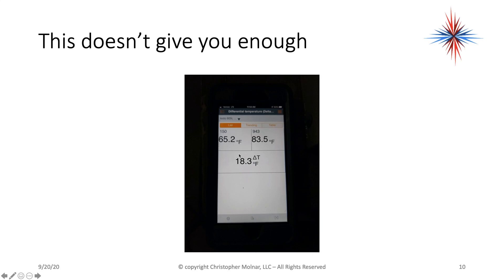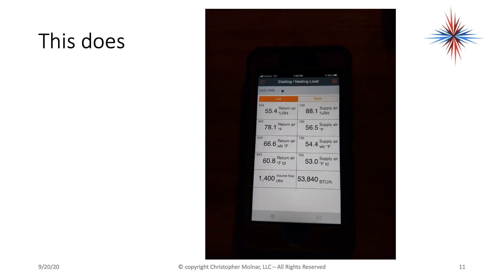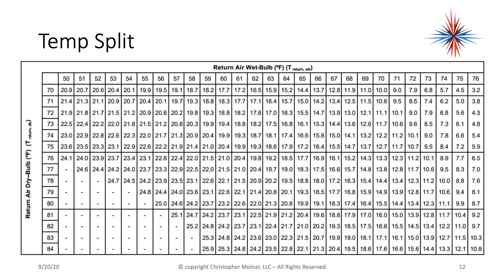For example, I have an 18.3-degree temperature split here — but is it right or wrong? You don't have enough information. Now if I take my return air dry bulb, my return air wet bulb, and my supply air temperature, now I have enough information, because I can compare it to a temperature chart.